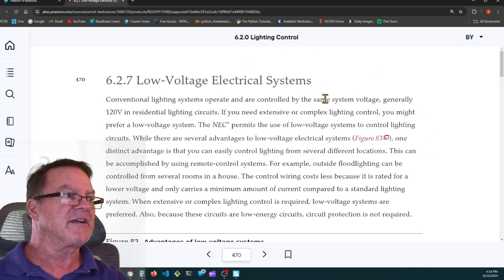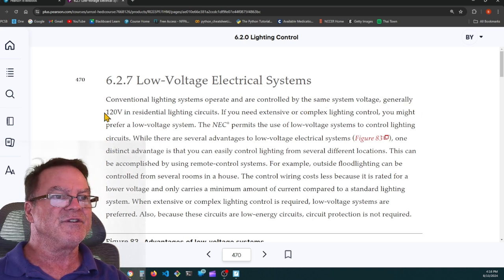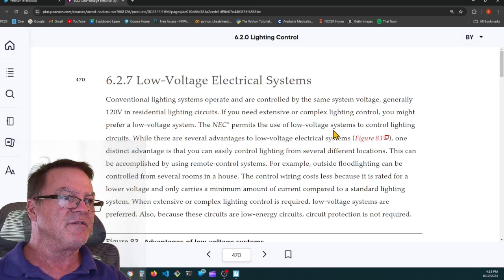6.2.7 Low voltage electrical systems. Conventional lighting systems operate and are controlled by the same system voltage, generally 120 volts in residential lighting circuits. If you need extensive or complex lighting control, you might prefer a low voltage system. The NEC permits the use of low voltage systems to control lighting circuits. While there are several advantages to low voltage electrical systems, one distinct advantage is that you can easily control lighting from several different locations.